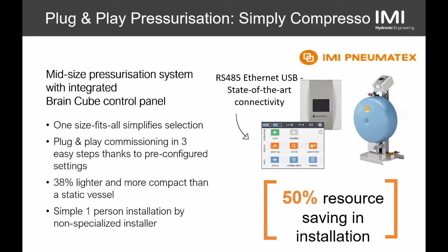Let me take another example from the pressurization range. The Transfero Connect is a high-efficiency system with pumps, but in this product we've also included a cyclonic vacuum degassing system for degassing the water makeup and system water in the most efficient way. This 3-in-1 combination doesn't only heavily decrease installation time and optimize system compatibility, but it is also cost-saving.